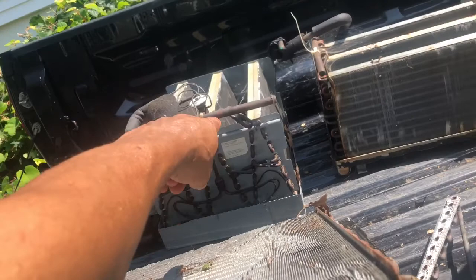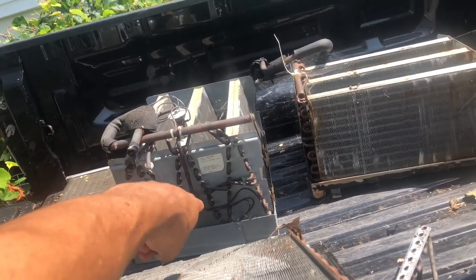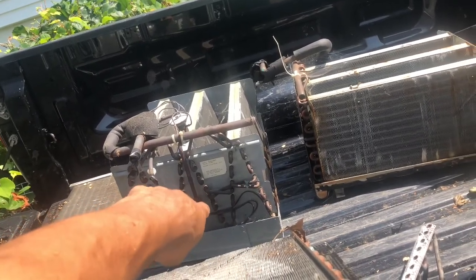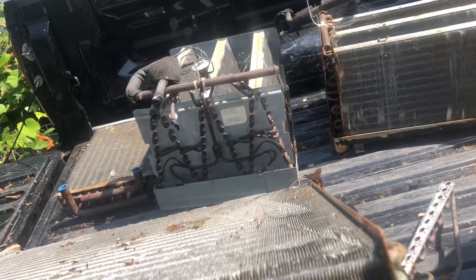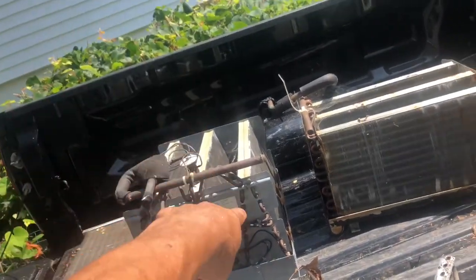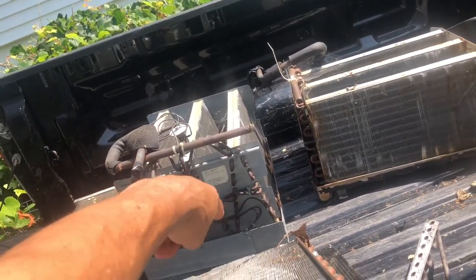It's weird, right? Because it's got the TXV right there on the top, but it looks like it also got an orifice there — look. Maybe they took the orifice out down the bottle there. Weird. I might keep that coil to play with it, make a video, see if it leaks or not — stick it in one of those buckets of water.